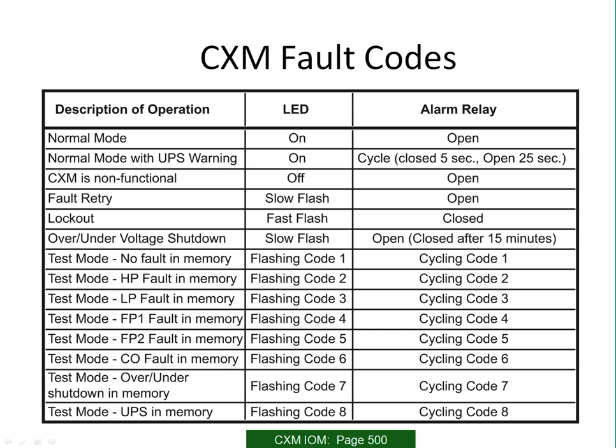So again, for example, if you counted a flash code 6, in other words, it's flashing 6 blinks, it pauses, and it flashes 6 blinks again. CO, fault in memory, that's condensate overflow. That's kind of how you translate what that information is from the CXM board.